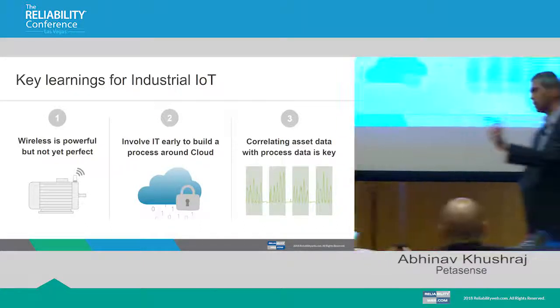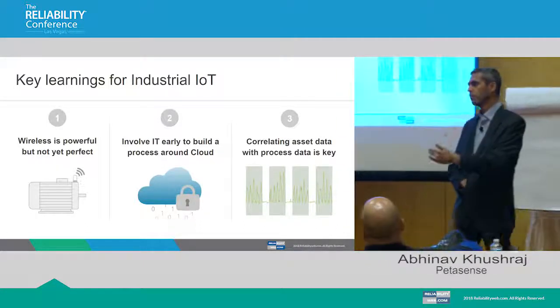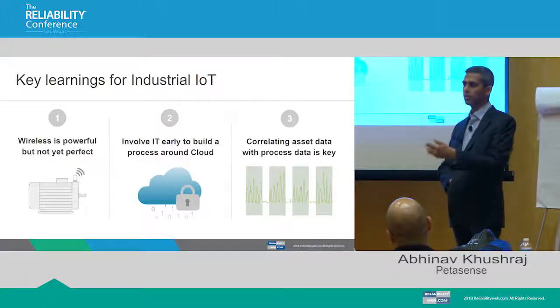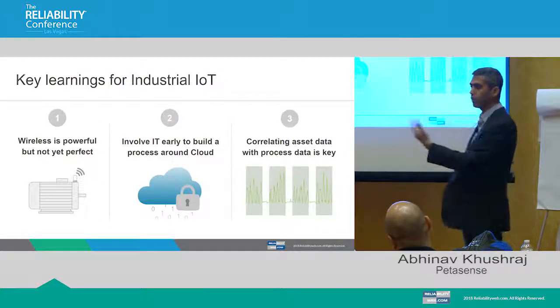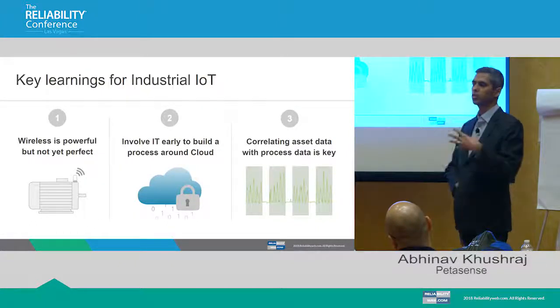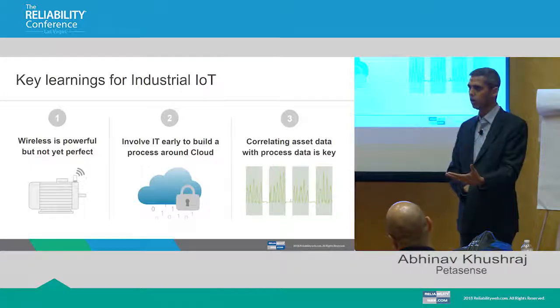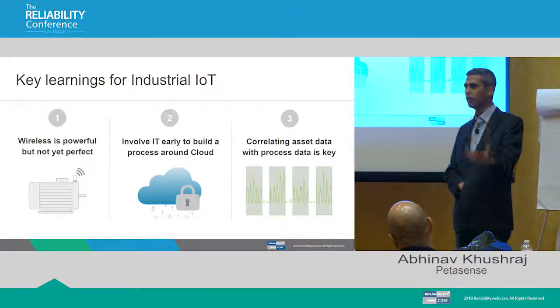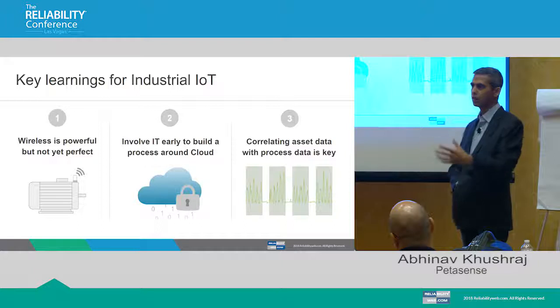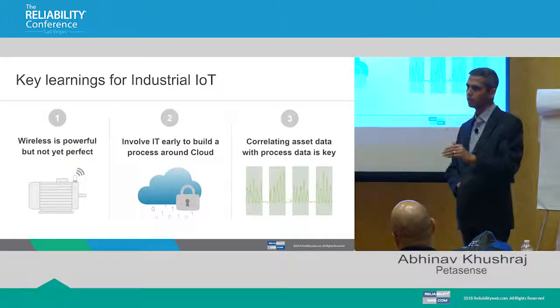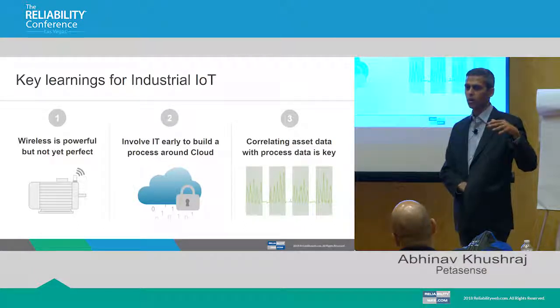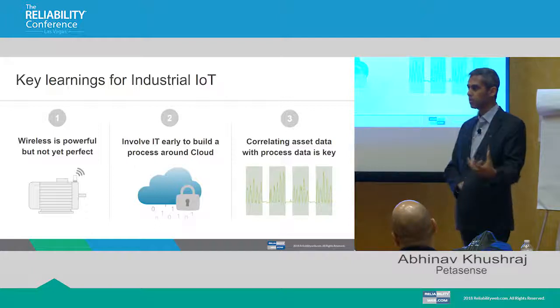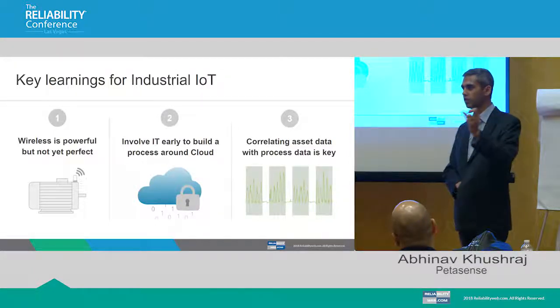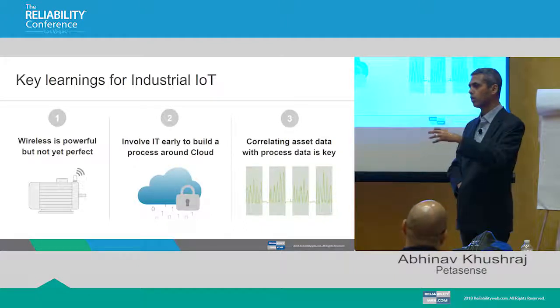In terms of the machine learning part, the data scientist doesn't look at the data every single time it comes in, or even when invoked. The data scientist has built a model based on asset classes—fans, compressors, air handlers, and so on—understanding their failure modes, where the sensors are placed, the machine information, running speeds, whether it's VFD or non-VFD, and all that. That model is what creates a health score.